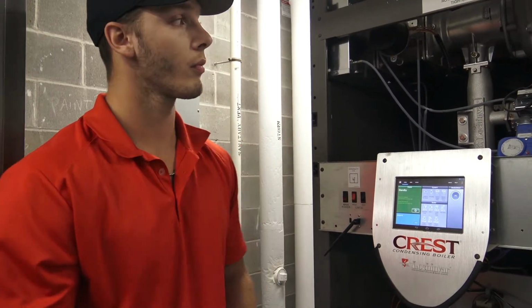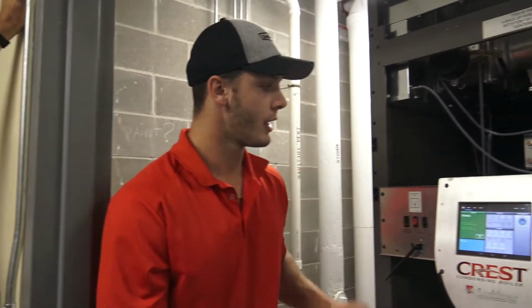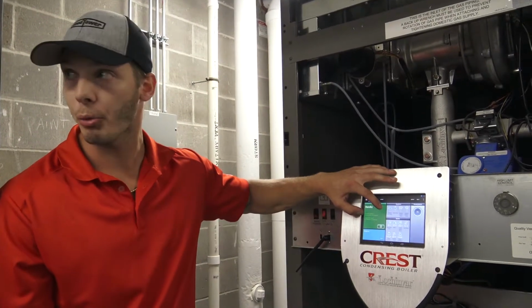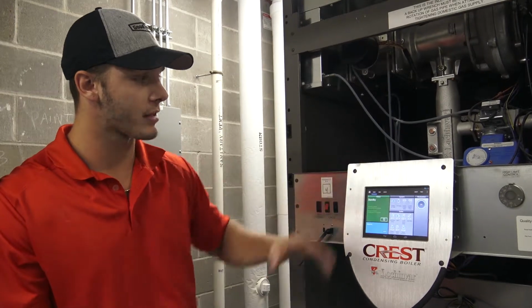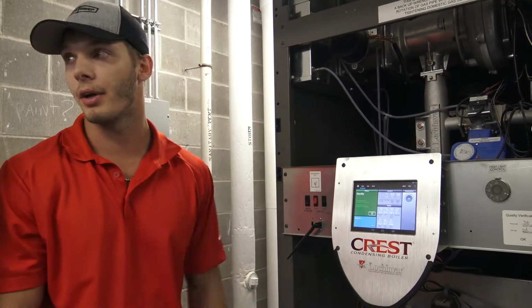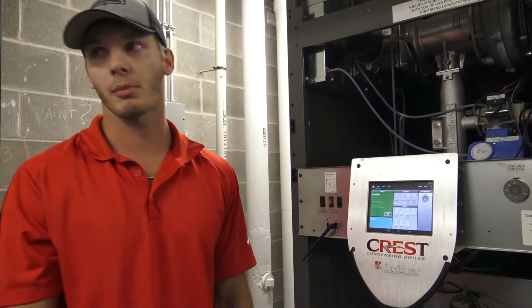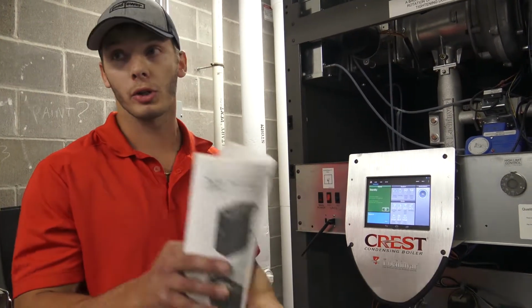So they automatically reset, but do you have to reset it on the face of the boiler? Yes, if it is a lockout. So it'll try to fire. It'll let it happen 3 times on the soft lockout. After that, it's going to do a hard lockout. This screen right here is going to pop up red, and obviously to reset that fault, you would hit the reset button. Under normal circumstances, you should not have that issue. The boiler should not be shutting off in high fire. It should constantly modulate down before it turns off.